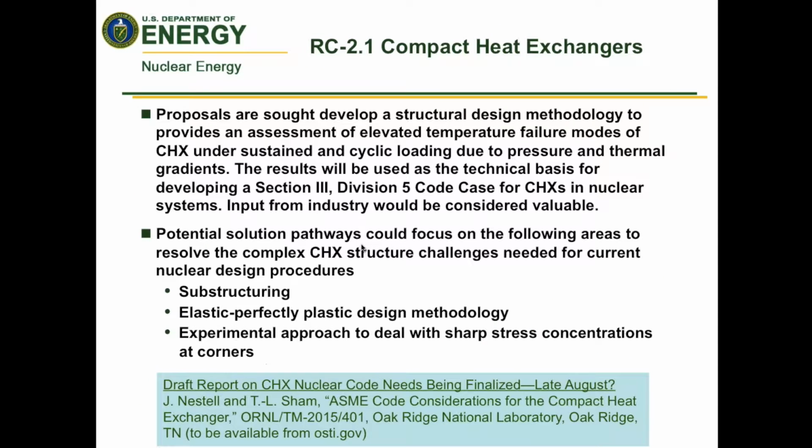So what are we looking for? We're looking for proposals to develop a structural design methodology that would provide an assessment of elevated temperature failure modes for compact heat exchangers under both sustained and cyclic loading due to pressure and temperature gradients. And the results from this would be used as a technical basis to establish the rules in ASME Section 3, Division 5 for the use of compact heat exchangers in nuclear systems.